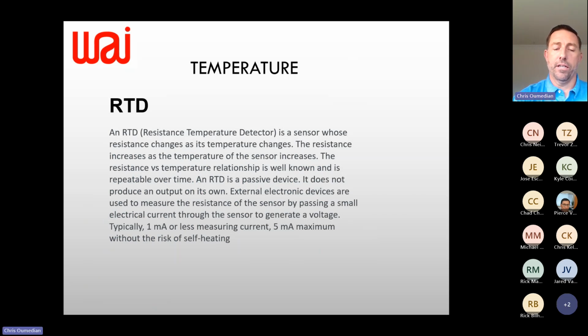Temperature, RTD. So for temperature, there are several different technologies to measure it. RTD is one of those technologies, and it stands for resistance temperature detector. Typically they use platinum as the metal. It's a sensor where the resistance changes based on the temperature, and there's a lookup or calibration chart based on what metal is used. There are ones that use copper, brass, and other metals. Platinum is the most common.